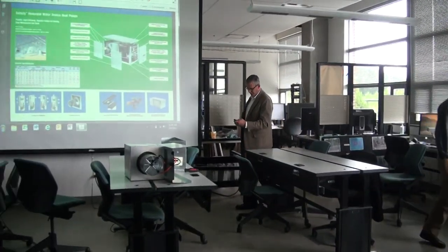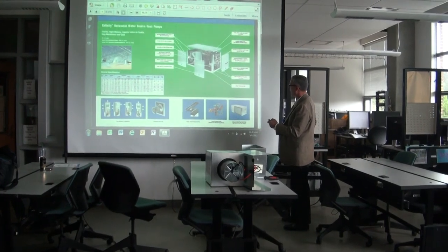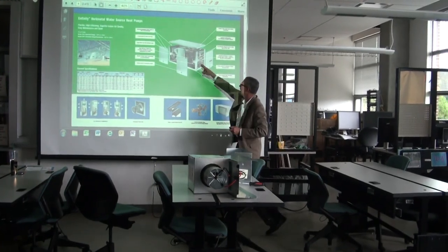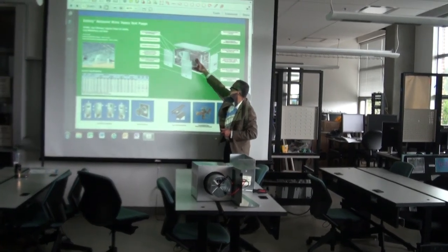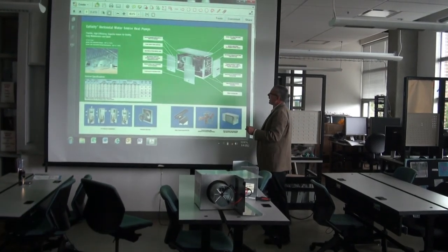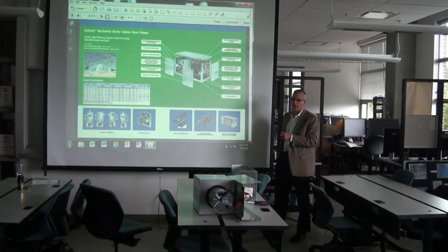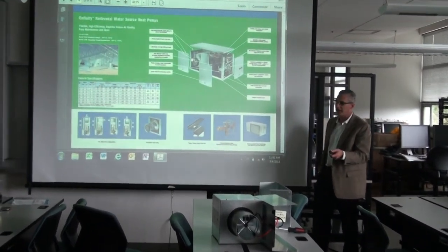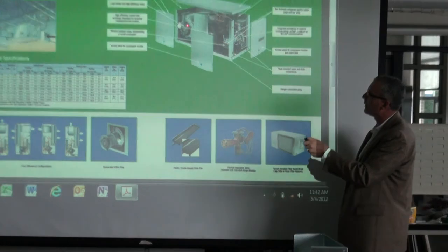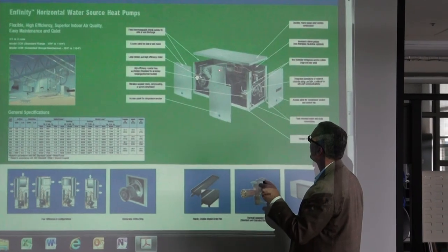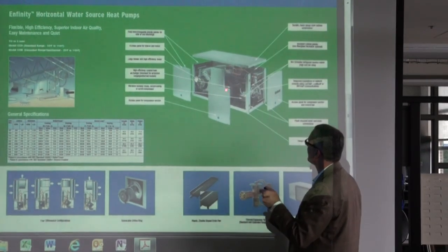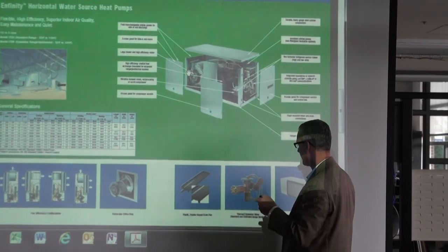Again, a water source heat pump uses a coaxial condenser. You can see this one's insulated with black neoprene-like insulation. And an air source heat pump, where you go air to air, would have another coil and fan, much like an evaporator fan and coil. So you can see there's the evaporator fan, there's the coil, piping connecting, and this is the water side condenser coil that has the tube in tube.